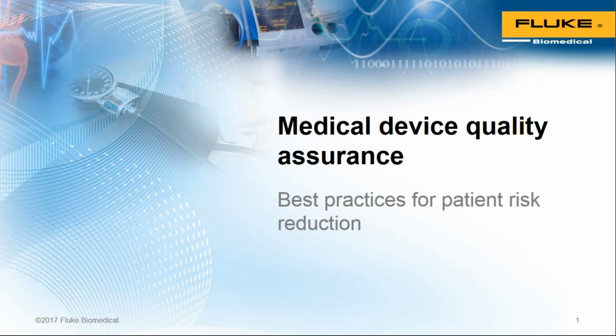economic reason to do that work, and that is that the studies have found that if we run till fail, if that is our strategy, and we took that same strategy no matter how critical or sophisticated the device, it will cost us 30% more on a run to fail strategy than it will if we do the preventive maintenance. So right away we know if we do the scheduled maintenance, the preventive maintenance, in accordance at the frequency the manufacturer recommends, we're almost sure that we will be able to save, not spend, 30% of whatever we would have spent. So how much is that?